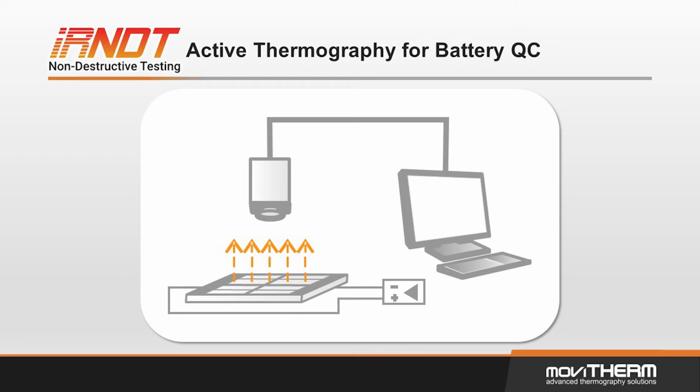So that's where active thermography comes in, where we actually excite that piece of material by any means that are useful. It could be a tiny little infrared emitter that just creates a little heat spot on it, and we may be scanning across the surface and observing how the thermal conductivity changes on the surface over time. That's where active thermography comes in, where we try to find any sort of changes in thermal conductivity and convert that into a result image, which then has that thermal contrast.